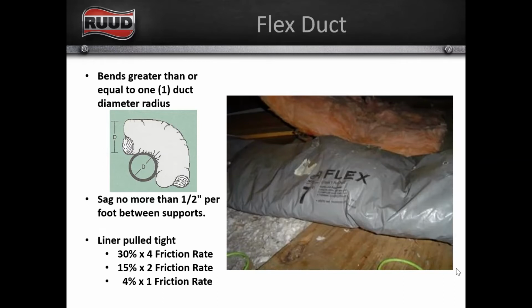And you can see I got a little drawing here, or a diagram, on the upper left where it shows the diameter of the flex run, and then the diameter of that turn. The larger, the better, right? So the more sweeping turns you can have in your flex run, the easier it is to push the air through. You want the ductwork to be supported and to have no more than a 1/2 inch per foot of sag between your supports. And a lot of times, if you go and look, you'll see that there's a lot more sag and a lot more play in a duct run.